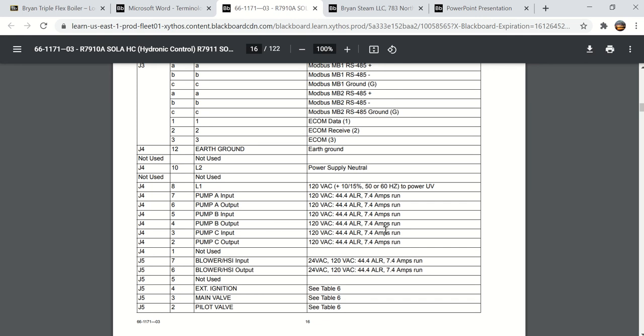But what you're seeing here is that with the 3 dry contact points that they provide for pump control, and these are programmable, you can actually go into the configuration and change how these contacts operate, or in what sequence they operate. But you cannot connect anything that has a run amps of greater than 7.4. You can't connect anything with a voltage over 120 volts AC, and they give you a locked rotor amps.